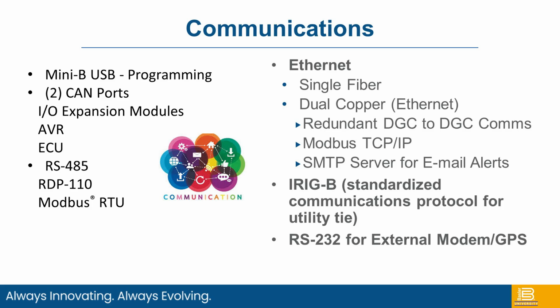In the dual copper option, we offer a redundant DGC to DGC communications, so that if for some reason the wire gets broke between one or another in a multiple gen application, the redundant DGC communications on the Ethernet will take over. Then we also can utilize one of those Ethernet ports for Modbus TCP IP, and we can also utilize that for the email alerts that we talked about earlier. Another form of communications we have on board is IRIG-B, standard protocol for the utility tie communications, and then RS-232 for external modems or GPS.